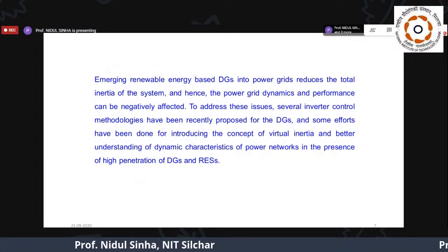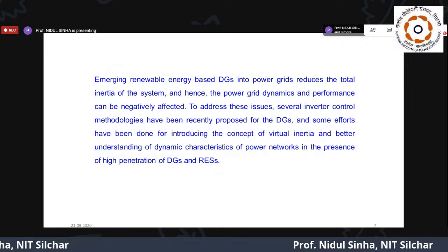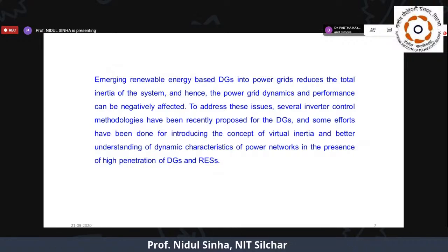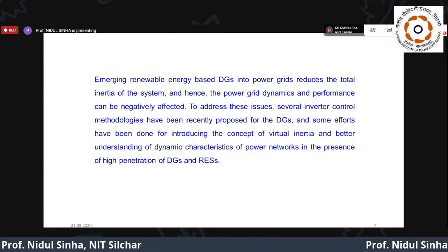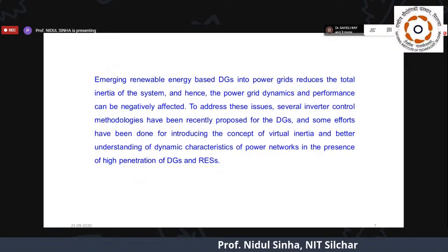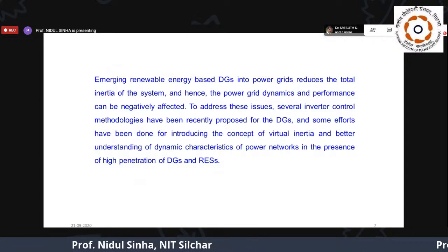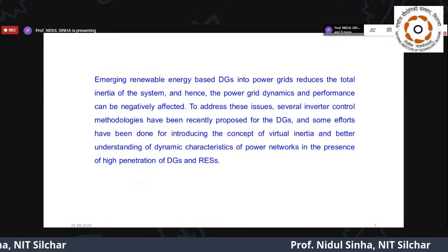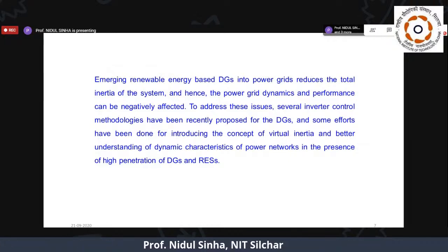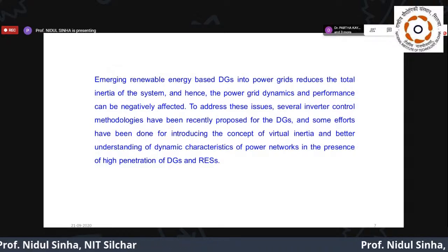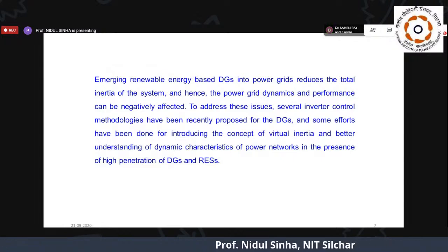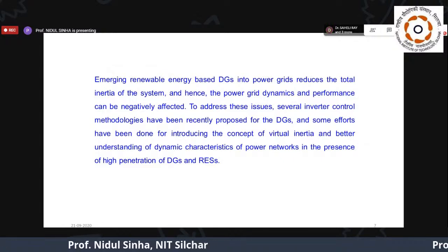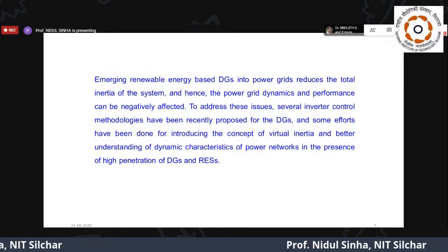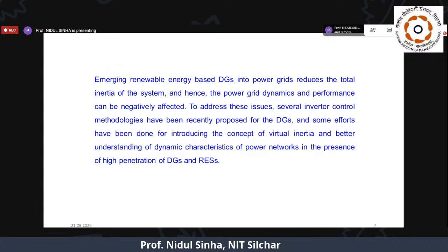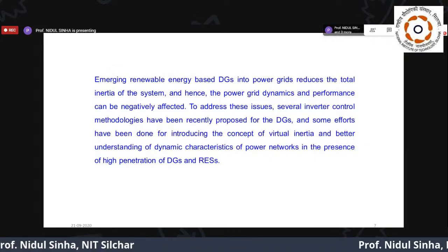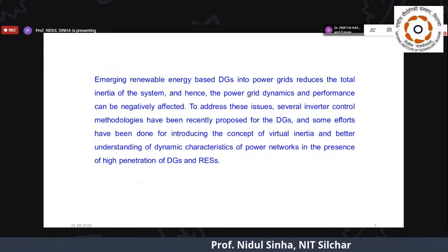Negative damping is very much pronounced when you have capacitive power factor of the power system, which is very much unwanted. Engineers prefer to have a lagging inductive power factor to be prevalent, so that the system becomes more stable. Specifically when you have zero power factor or capacitive power factor, together with a fast excitation system, there is every chance the system will collapse and voltage instability will occur. So to overcome this negative damping, we add positive damping to the system.